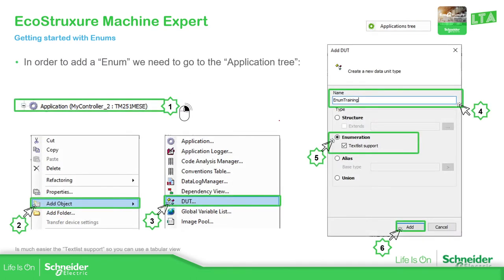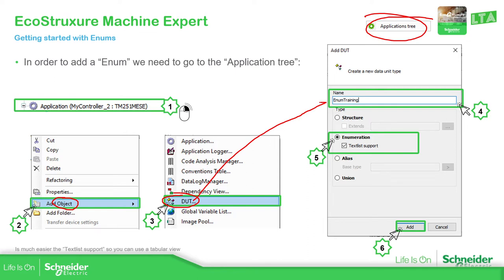In order to add the enum, we just need to go to the controller in the applications tree, right-click, select add object, and then we need to find in our view the DUT. Then you just need to change the name to the one that you want. Be careful on the name — try to do something easy to understand. And then here you have the possibility to select enumeration. Here is something important: if you don't remember the structure, try to use the text list support because it's very useful. Then click Add.